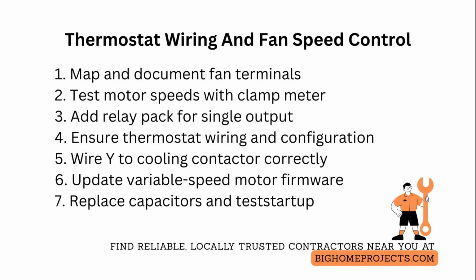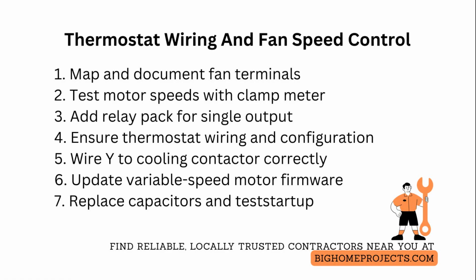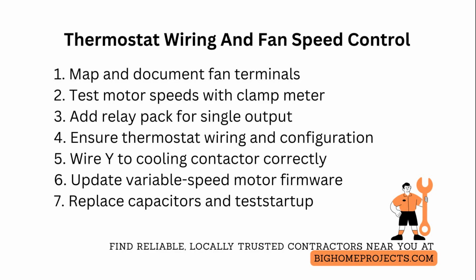Advanced thermostats that modulate blower output require compatibility with the furnace control board's signal type, either simple on-off or variable frequency drive. Verify that the cooling contactor call on the outdoor condenser is wired to the Y terminal so the control board can switch to the higher cooling fan speed automatically.